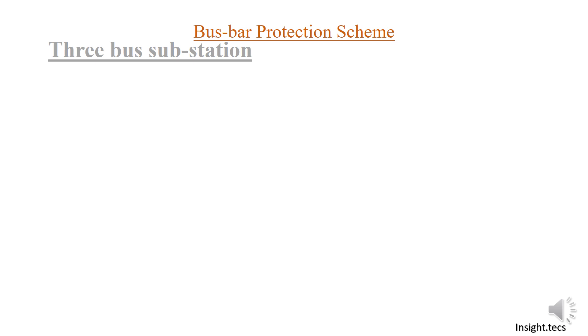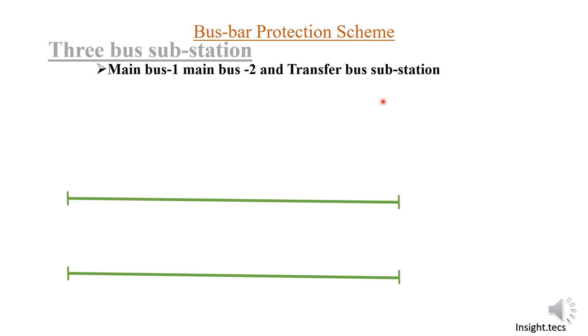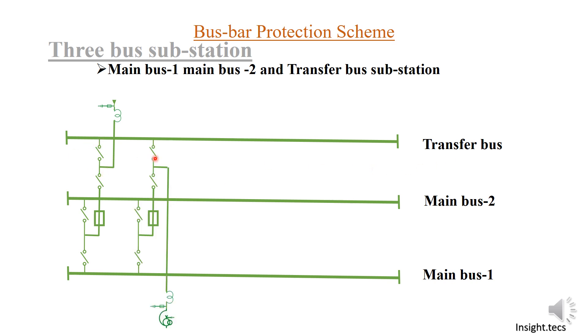Now before going into the second type of bus, we will discuss in detail about the three bus substation. This is Main Bus 1, Main Bus 2, and Transfer Bus substation. Similar to the two main bus scheme, we have Main Bus 1 and 2, and as we discussed with the auxiliary bus, we now have a transfer bus scheme — a combination of main bus and auxiliary bus. The arrangement has bus selector isolators 1 and 2 through which you select which bus to charge. One more isolator is added for the transfer bus.